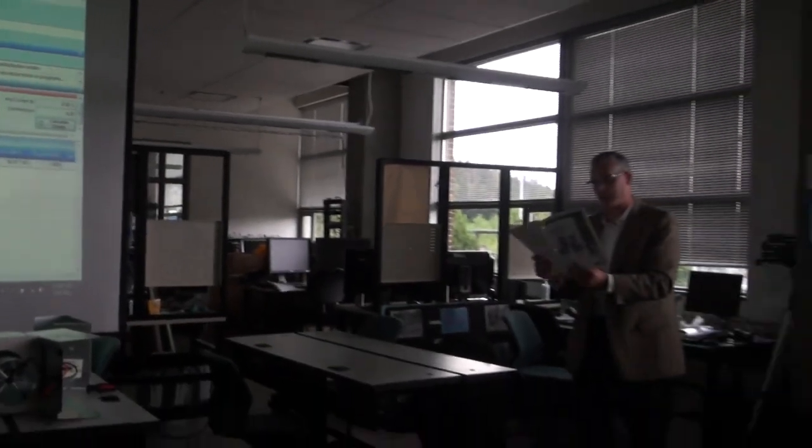So, in the typical catalog for any of the manufacturers, you're going to have operating limits. I'll just mention a few of them. So there's air side limits and there's water side limits. And heat pumps, any kind of refrigeration cycle, the equipment is ignorant. It just knows it doesn't want low pressure, it doesn't want high pressure, okay? And those are associated with temperatures, so low pressure, low temperature, high temperature. And to keep it in those boundaries, heat pumps, like other equipment, are designed to not have a lot of variance in airflow and temperatures.